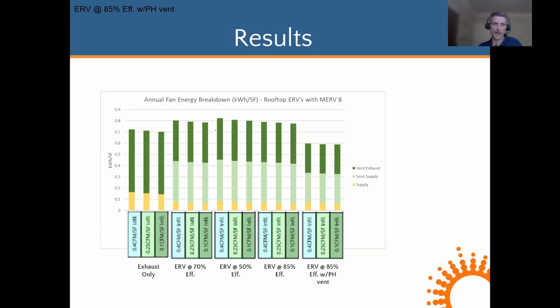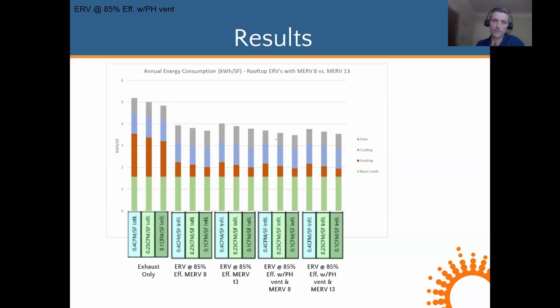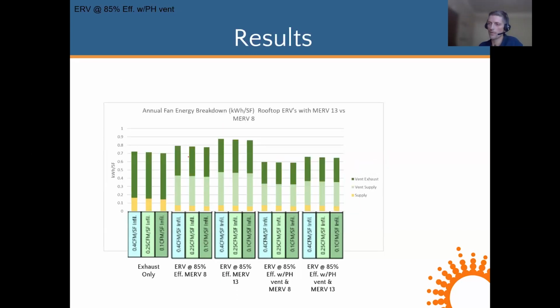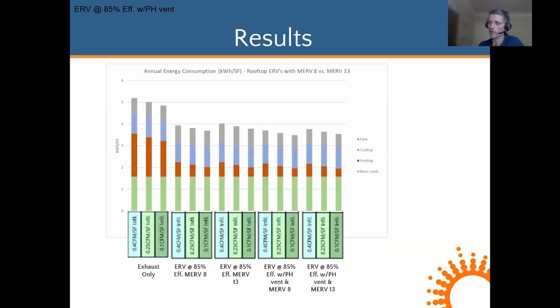Finally, looking at our rooftop ERV, MERV 8 versus MERV 13, still much lower than the exhaust-only scenario. And our fan power with the MERV 13 filters does definitely increase now. We're looking at about 0.1 kilowatt hours per square foot of increase from MERV 8s to MERV 13s in just the fan power. But overall, total energy savings still much lower.